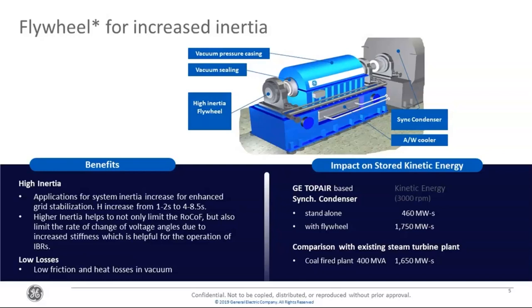And the one thing to mention here, I think, would be that as opposed to synchronous generators, where once the inertia response dies out, the primary frequency response kicks in and helps re-accelerate the machine back, in the case of synchronous condensers, you can allow it to decelerate for a few seconds, but at some point it has to re-accelerate back to synchronous speed, at which point it will draw some power from the grid, right? And the flywheels are usually encased in their own vacuum casing, and that's primarily to prevent or reduce windage friction and heat losses and so on and so forth.